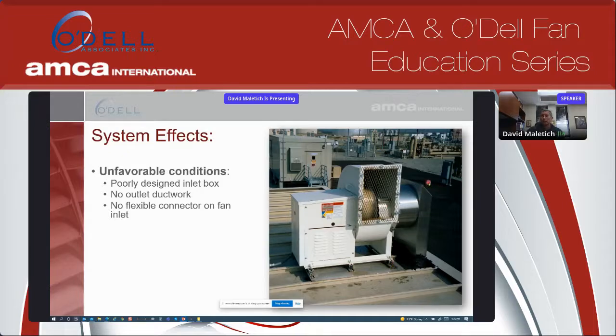Also, what you're going to see in the video presentation a little bit later, the aspect ratio of this inlet box is very poor, which shoots the air too high into this duct here. So we're only using the top portion of the wheel to move the air. The bottom portion of the wheel here doesn't see any air. So we're only going to use a portion of the wheel to move the air. Fan's going to underperform. Finally, we have no ductwork on the outlet, so we're not going to get any static pressure regain at that point of operation.